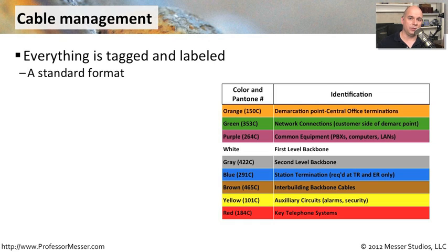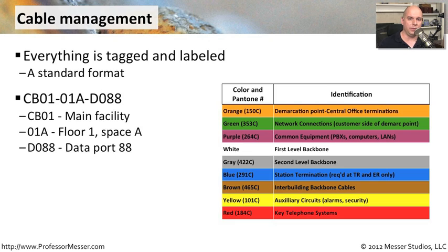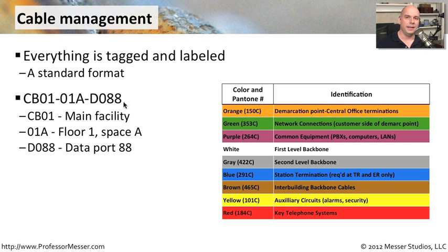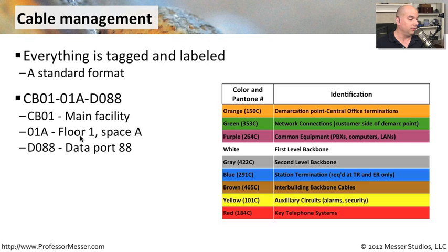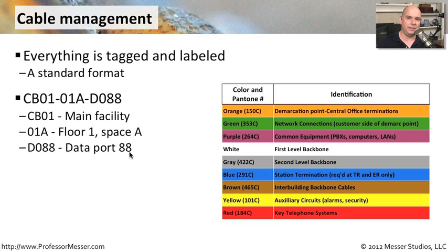The EIA-TIA standard we mentioned talks about ways to do this. Here's how you might tag one cable — that end of the cable is CB01-01A-D088. This may mean that CB01 is your main facility building, 01A means it's on floor number one in your A data room, and D088 means data port 88. That's a very specific labeling.